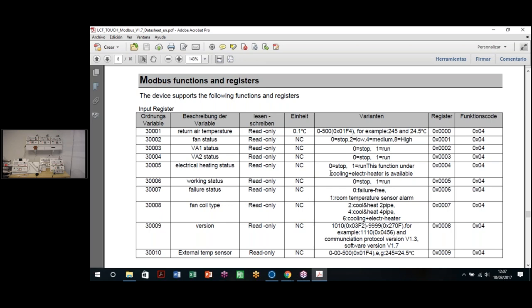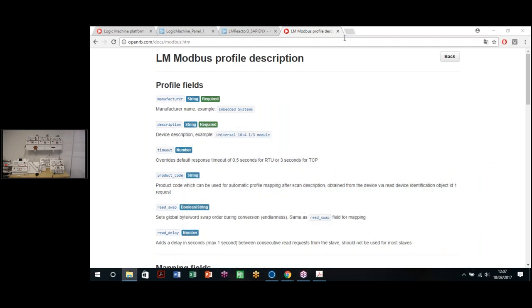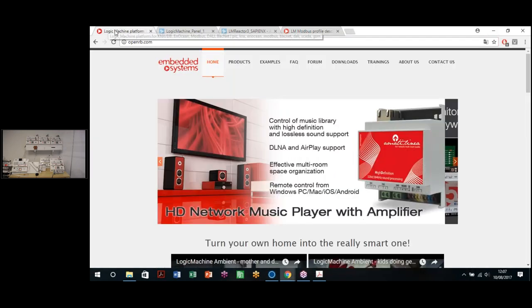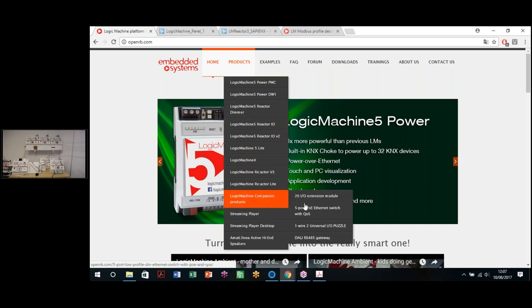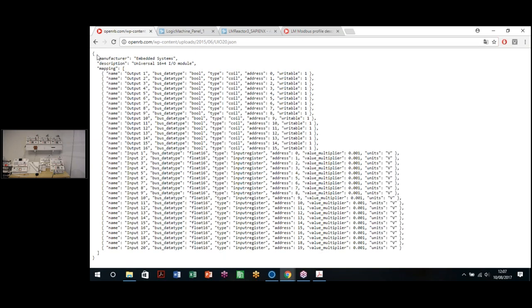Okay, now that we have the manual open, we need to use a profile. We have an example profile on the OpenRB webpage: the profile of the 20 IO extension module. This profile can help as an example on how to configure. This is the Modbus profile that we are going to create for that specific device, in this case, the thermostat. Here we can see the specification of the manufacturer, the description of the device, and the mapping of all the registers that we have.